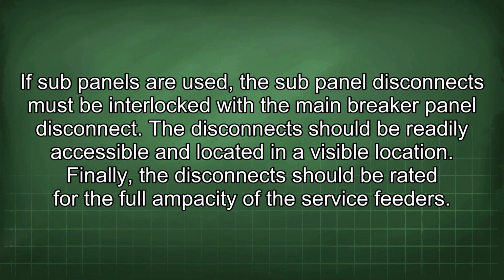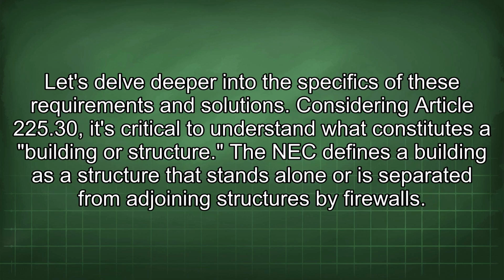If sub-panels are used, the sub-panel disconnects must be interlocked with the main breaker panel disconnect. The disconnect should be readily accessible and located in a visible location. Finally, the disconnect should be rated for the full ampacity of the service feeders. Let's delve deeper into the specifics of these requirements and solutions.